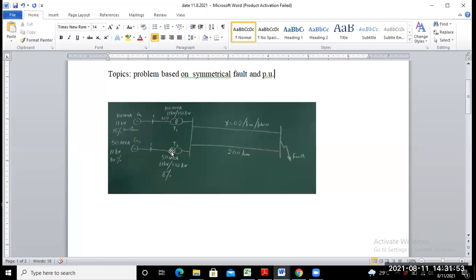Is it not? So now first step is to convert all the reactance value on the common voltage and common MVA rating. Okay. So first step, you choose the base value, voltage and MVA. Okay. So generally we try to select the base kilovolt or base MVA rating as the highest rating of the system. Okay, so what is the highest MVA rating or kilovolt rating in this system? Is just up to this point. This is the highest MVA rating and voltage rating. That we will try to choose as a base MVA rating and base kilovolt rating.